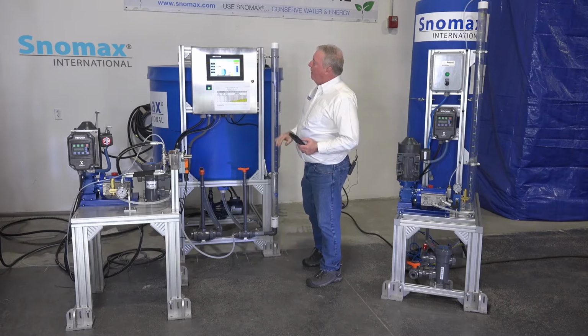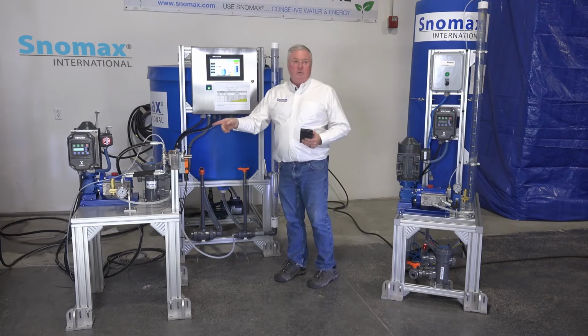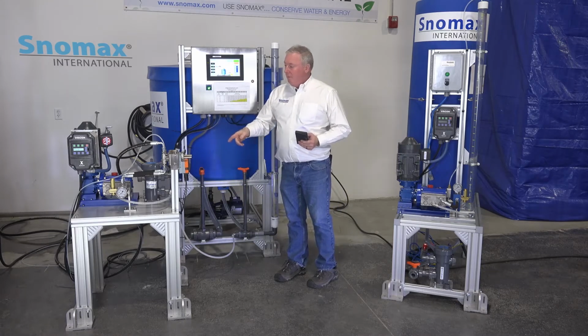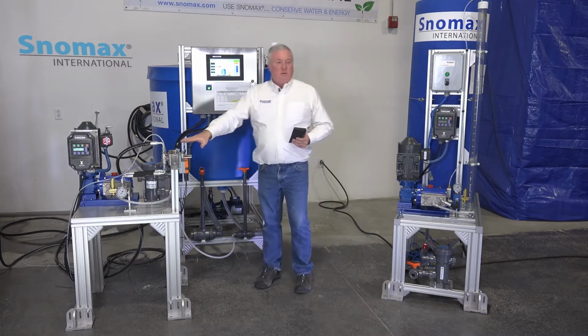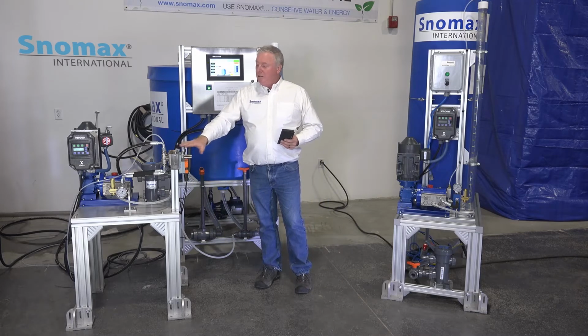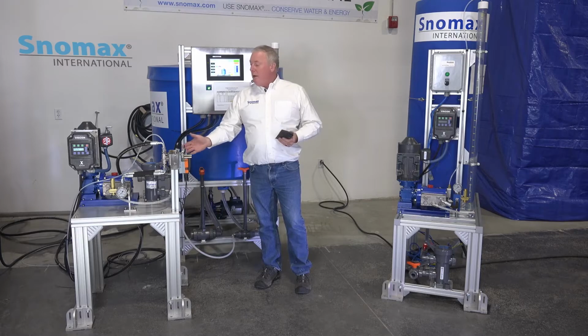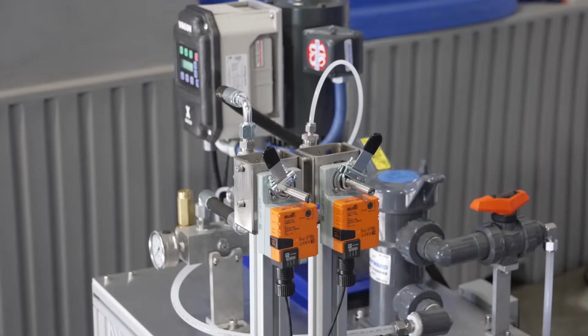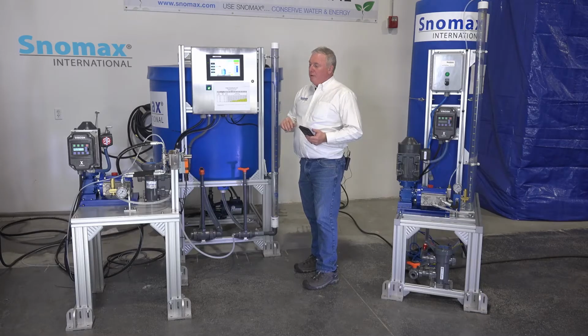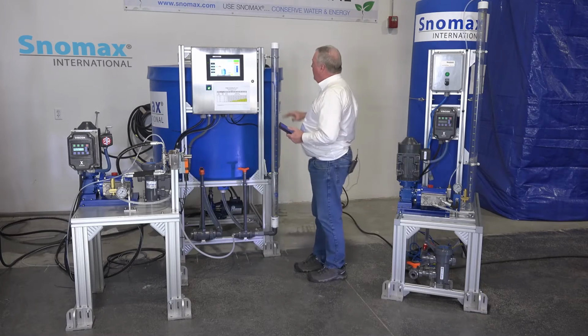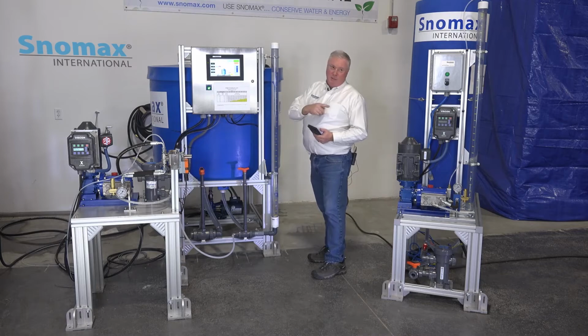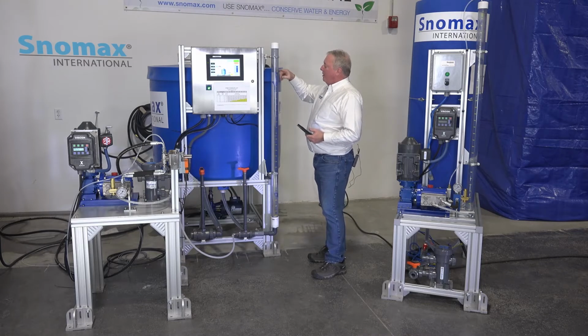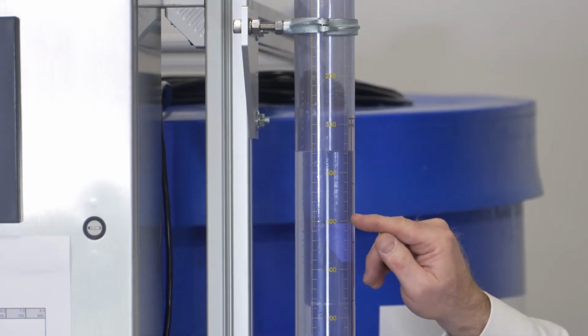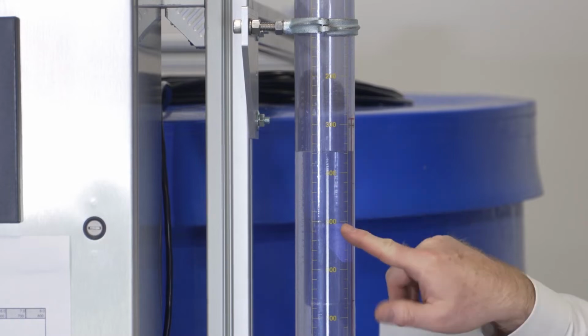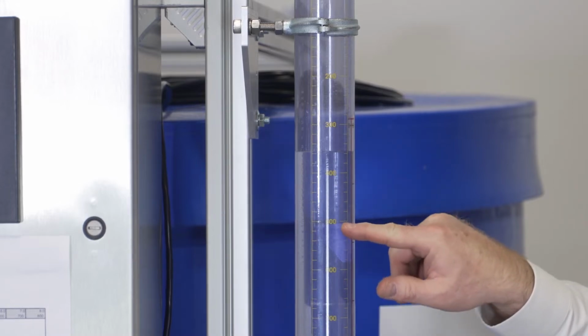pump. It's going to take a second or two for the pump to turn on. And then we're going to let these valves cycle. So they're going to take a second or two to rotate and get into the right orientation so that we've bled them out automatically. And now that the air is out of the pump, I'm going to come over here and we do the same thing we did on the smaller system. I'm going to pick a nice even number. So I want to use 500 as a marking on this calibration tube, just because it's a nice round number.